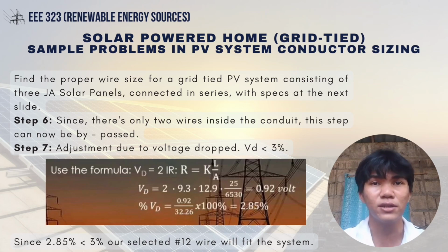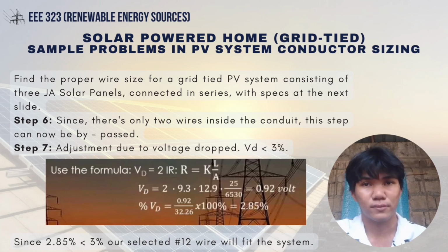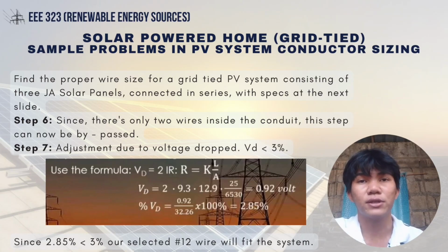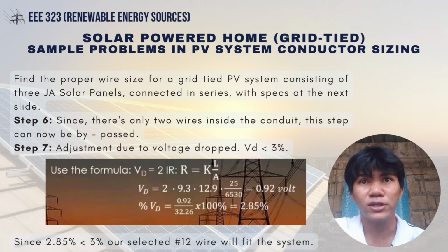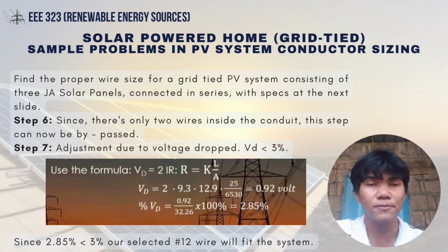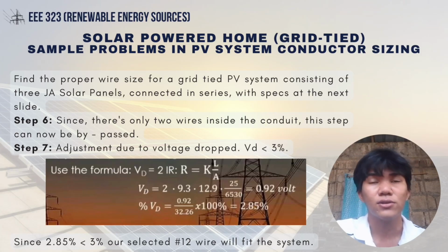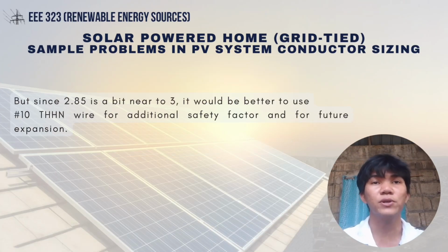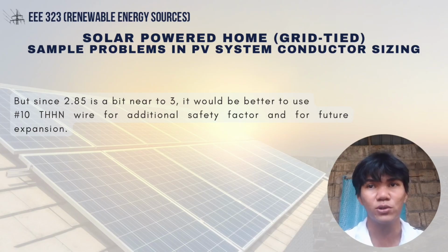So, percentage voltage drop is equal to 0.92 over 32.26 times 100%. So, may total voltage drop tayo na 2.85%. Since yung 2.85% is less than 3%, our selected wire is okay, so gagamit tayo ng number 12 wire sa system. But since 2.85 is a bit near to 3, it would be better to use a number 10 THHN wire for additional safety factor and for future expansion.